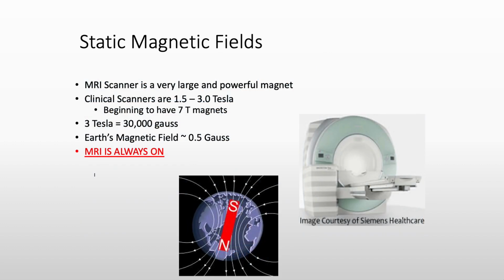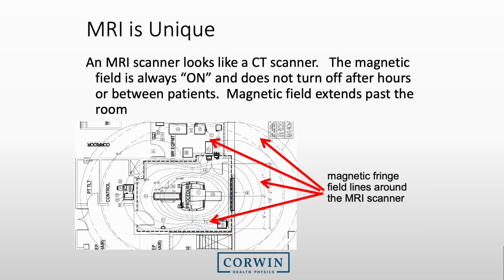Since most of you are MRI technologists, you are all quite aware that the MRI system is a very large magnet. We need to continually emphasize to others that this magnet is always on. The magnetic field from the MRI system is unique from other imaging equipment's hazards. For instance, we typically understand that a computed tomography system, or CT system, which operates with ionizing radiation, will only provide radiation within the room itself, with very little going outside the room. With MRI, however, the magnetic field will often exceed the boundaries of the room. In the diagram here, we see that the magnetic field from this 3T magnet exceeds the boundaries of the room. Magnetic fringe field lines, which indicate the location and intensity of the magnetic field, are shown with concentric lines outside the MRI room. The magnetic field is continuously present.